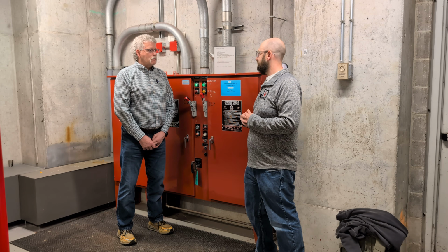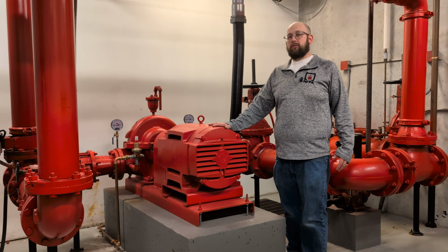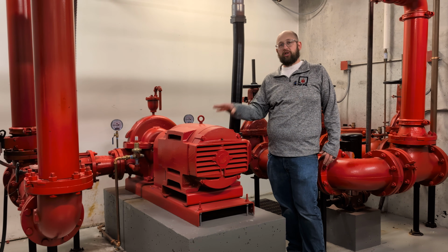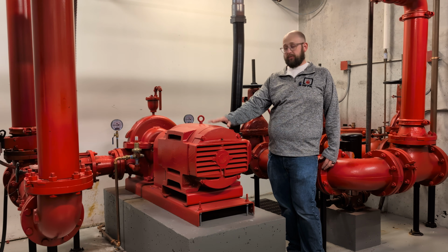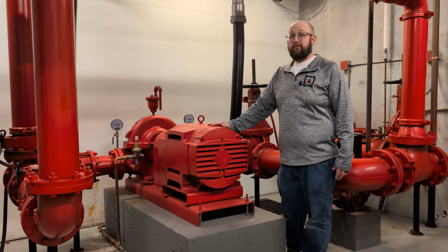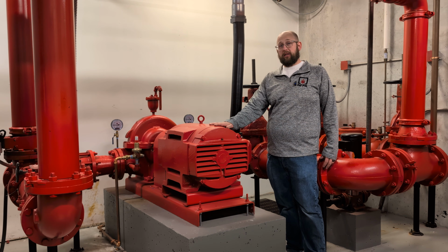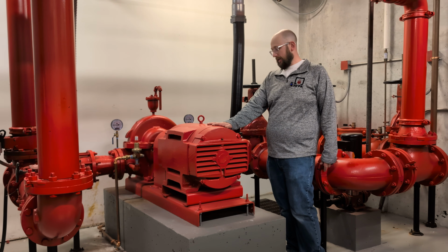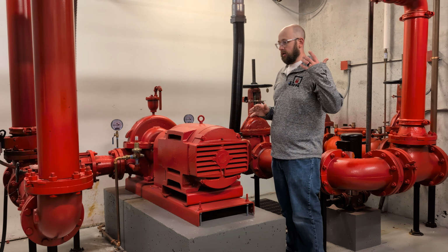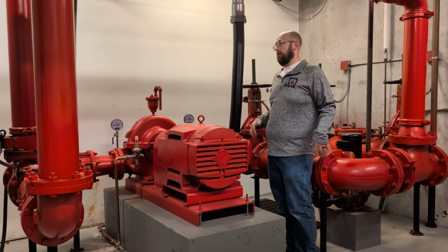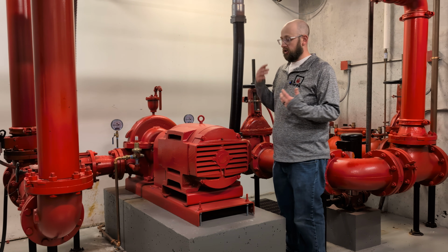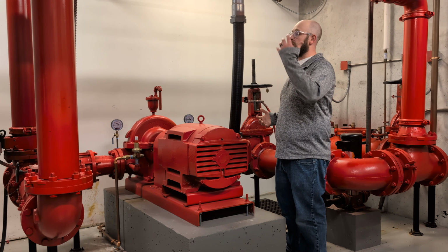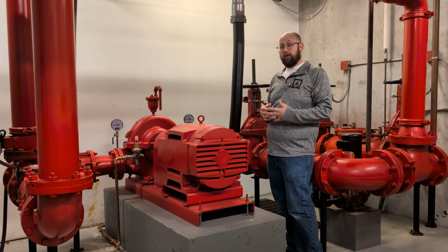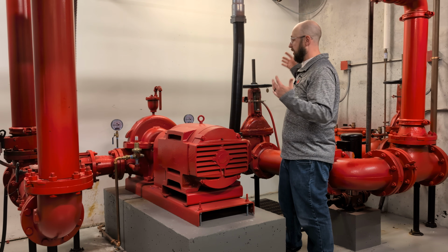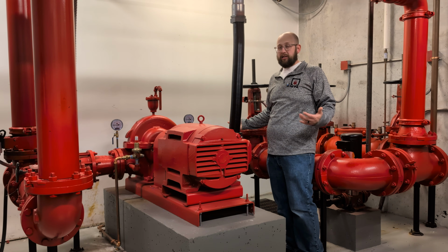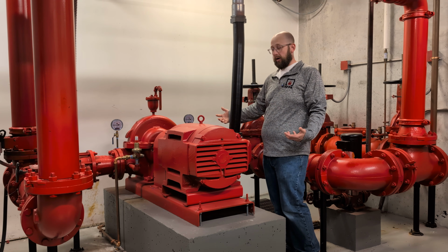Yes, not a problem. Another question we got was, what's the required inspection and testing for electric fire pumps? All of that comes out of NFPA 25, the standard for the inspection, testing, and maintenance of water-based fire protection systems. Basically, we're required to do a weekly fire pump room inspection, making sure there's no water on the floor, no leaks. We're checking that the valves are in the proper orientation, that we're properly heating the space so we don't have freezing conditions, and we're looking at the condition of the pump.